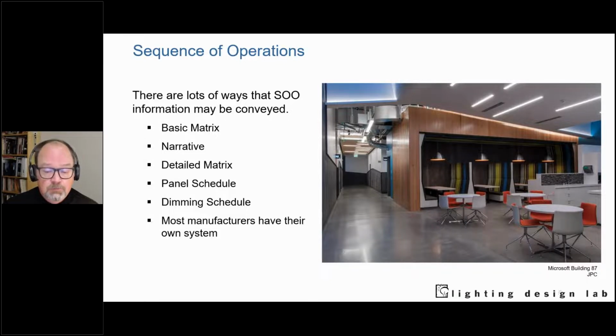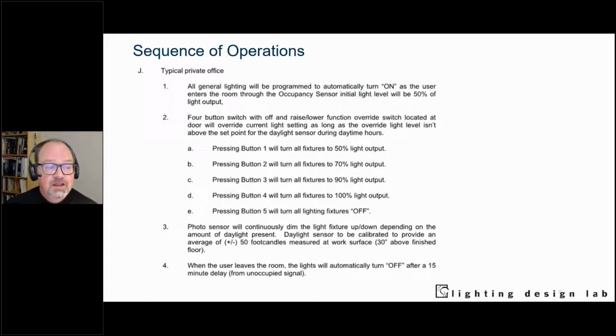A couple of examples. Here is a narrative-based sequence of operations. This is from the San Francisco Public Utilities headquarters building, from the typical private office on that particular project. You'll see that all general lighting will be programmed to automatically turn on as the user enters the room—that's an occupancy sensor—but it sets the initial level to 50% of light output.